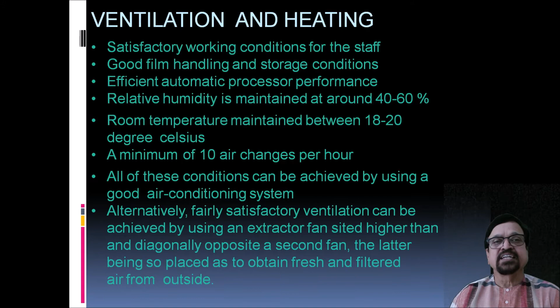The air conditioning system can recirculate the air, and it can also take fresh air from outside and put the cold air inside. Alternatively, satisfactory ventilation can be achieved by using an extractor fan, that is what we call an exhaust fan, placed higher than and diagonally opposite a second fan. So two can be achieved. The latter is placed so as to obtain fresh, filtered air from outside. So how is it achieved? Fresh air by the air conditioning. Air conditioning has a system by which it can pull fresh air from outside, also with the help of exhaust fans. The exhaust fans should be designed in such a way that they will really replace the air and should not hinder each other's working.